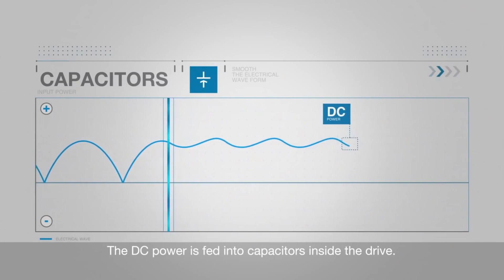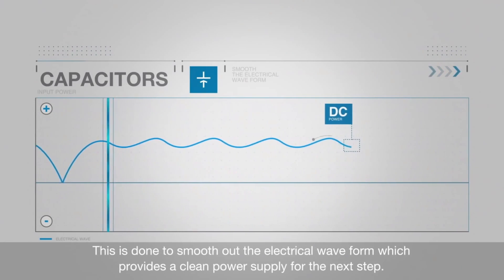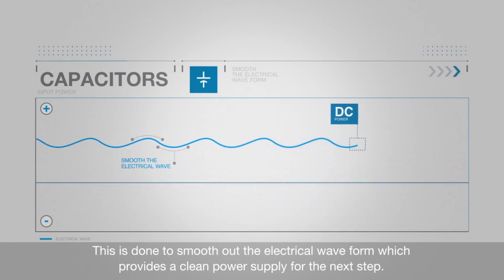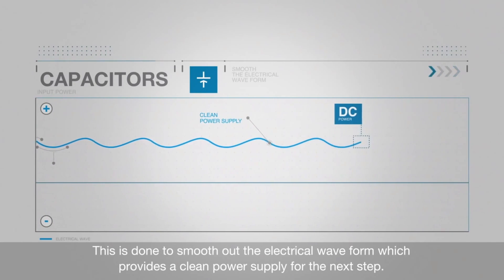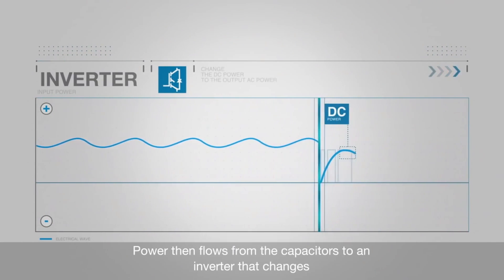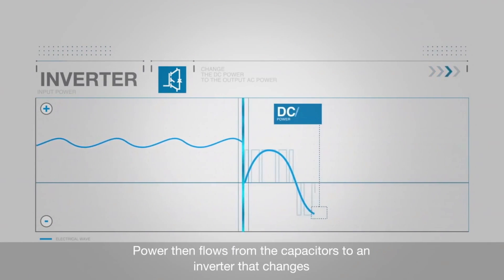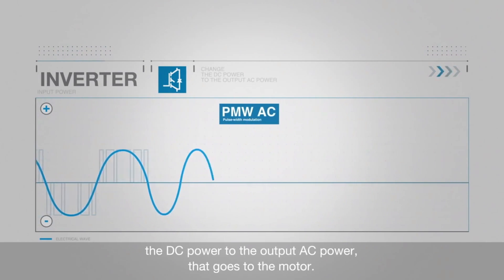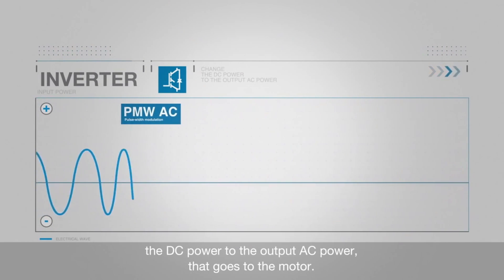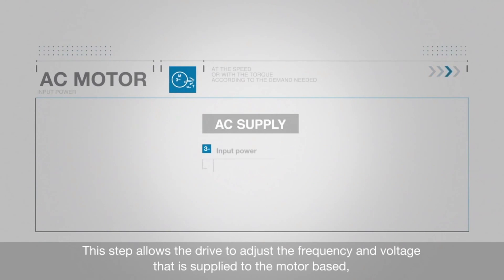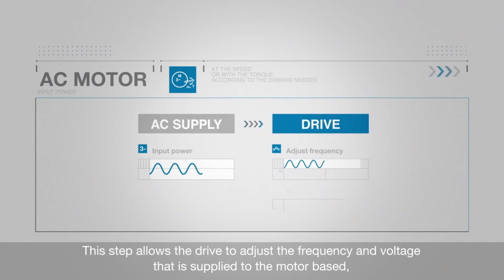The DC power is fed into capacitors inside the drive. This is done to smooth out the electrical waveform, which provides a clean power supply for the next step. Power then flows from the capacitors to an inverter that changes the DC power to the output AC power that goes to the motor.